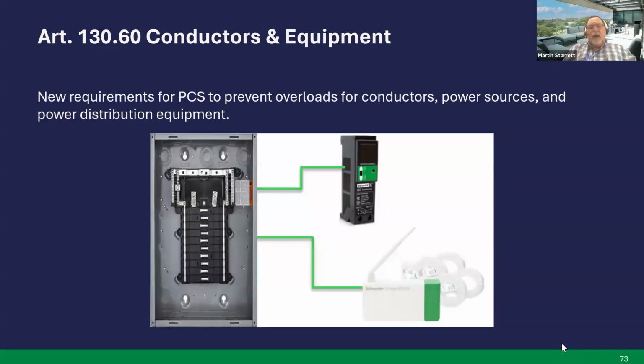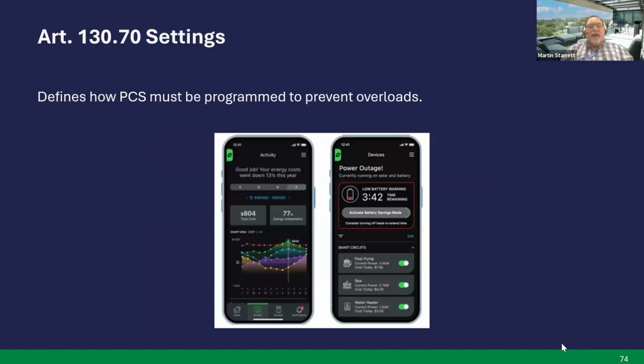Next slide. One of these is Article 130.60, conductors and equipment. There are new requirements for power control systems to prevent overloads for conductors, power sources, and power distribution equipment. Anything you need to know about conductor sizing for these systems will be in that 130.60. Next slide, please. 130.70, settings. That defines how the power control systems must be programmed to prevent overload. If you have been installing these systems, you might want to look at these articles in that Part 2, because there are going to be some new requirements. Next slide.